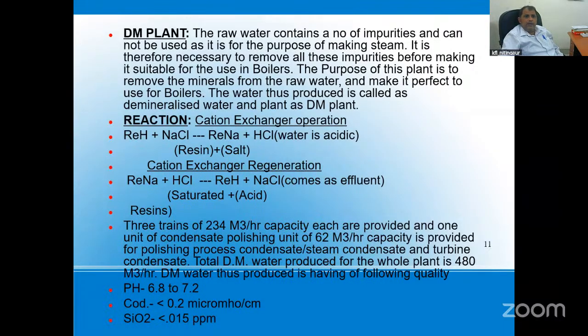So raw water contains a number of impurities and cannot be used for the purpose of making steam. It is therefore necessary to remove all the impurities before making it suitable for use in the boiler. The purpose of the plant is to remove the minerals from the raw water and make it suitable for the boiler. The water thus produced is called demineralized water, and the plant is called the DM plant.